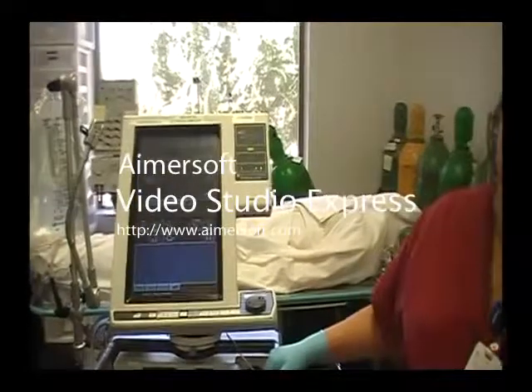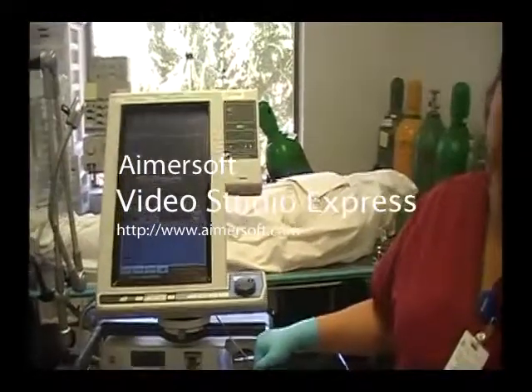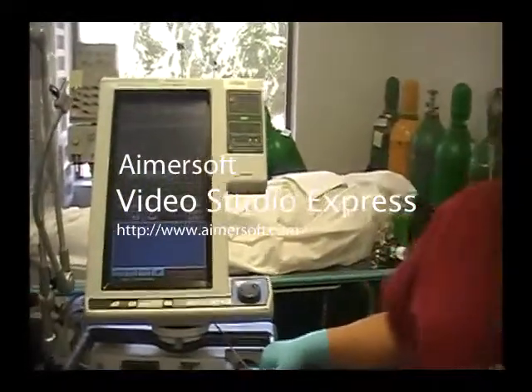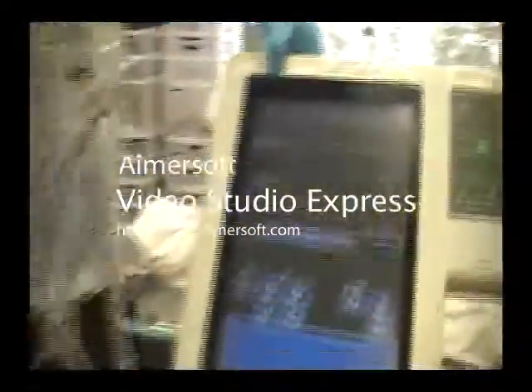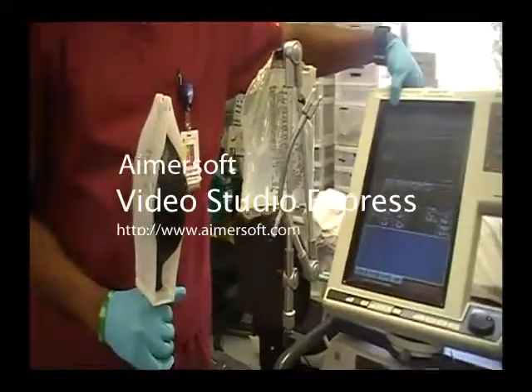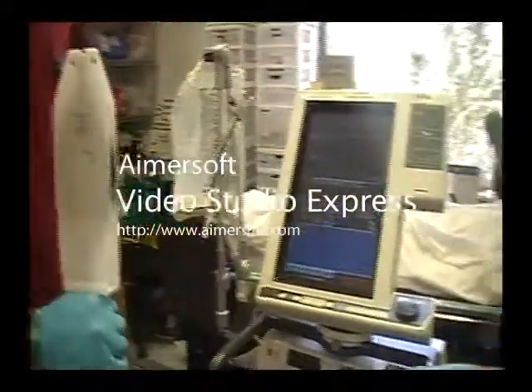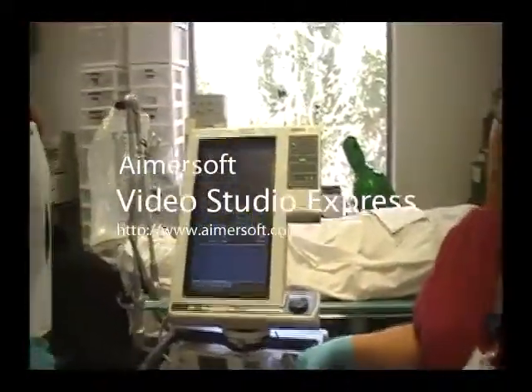Okay, we're going to observe the ventilator's working pressure, which is the peak pressure, with the test lung. You can see the peak pressure. It's in a normal range, working along with the test lung. We're going to observe proper function of the ventilator. We've got no alarms going off. Everything's functioning.